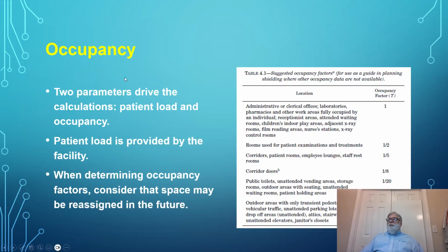The same person is only there for a fraction of the time, and that's why it's limited. As far as examination rooms, the person doing the exam, there are several people who do exams or procedures.